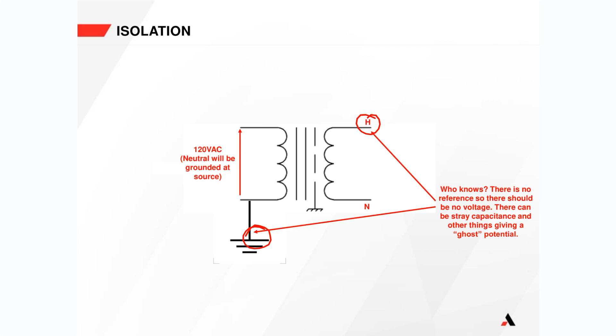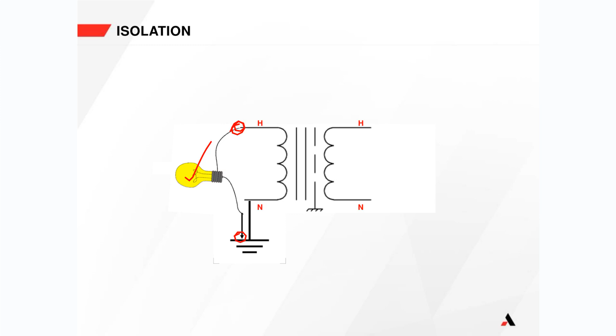Now, yes, there can be some stray capacitance and other things in the cables that could give a ghost potential if you measured it with a very high impedance voltmeter. But there is actually no direct connection, and therefore, if you connected a light bulb from hot to neutral on the input, yes, the light bulb would light, okay? But if you connected a light bulb from hot to ground on the secondary, the light bulb would not light. There is no current path. There is no connection to ground, so it would not light.